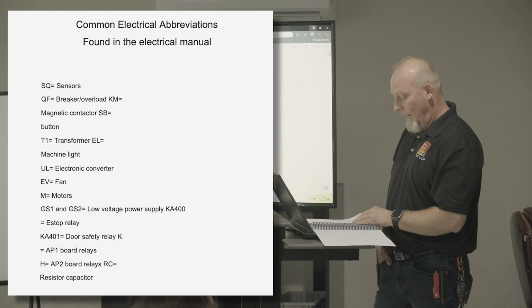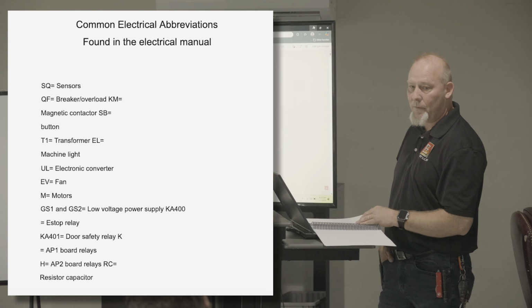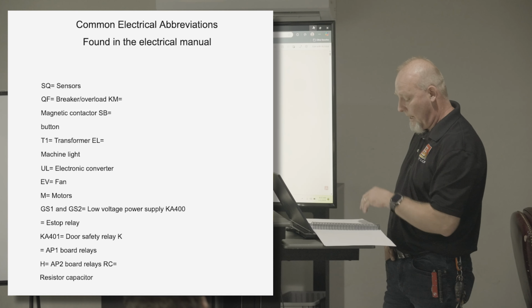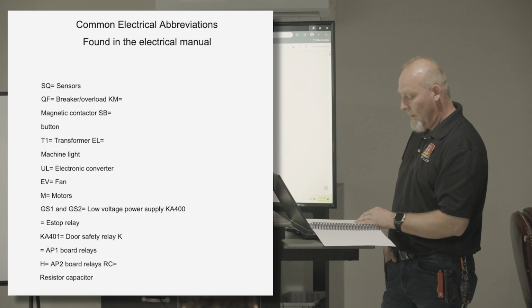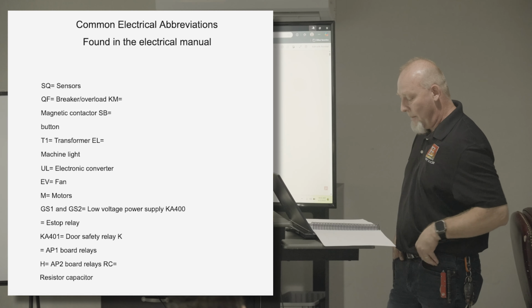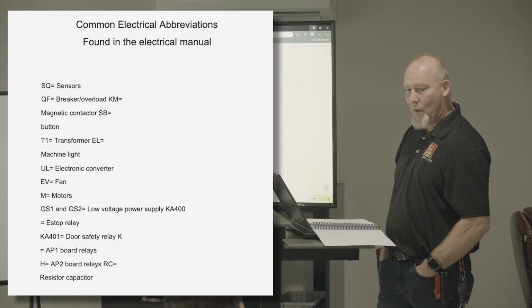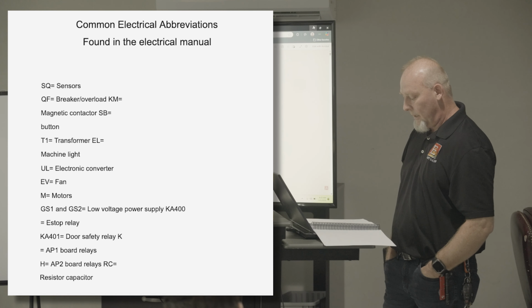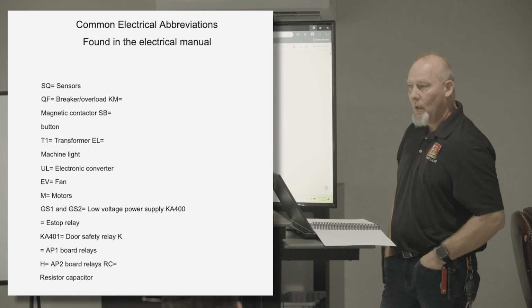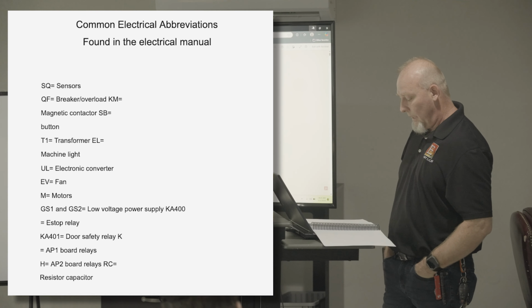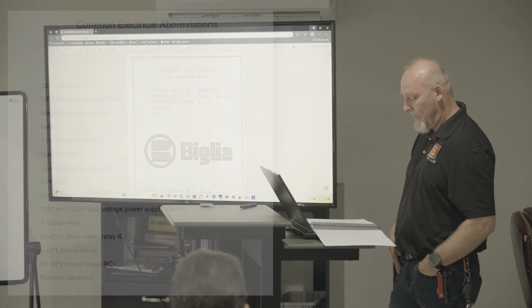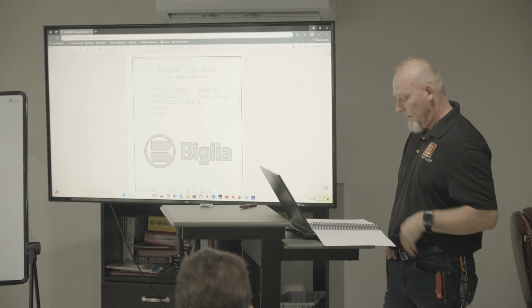The KA400-401 is our e-stop relay and door safety relay. There's been some changes on that now. We still have the KA400 for the e-stop, but now we're going through an AP board for the doors, which we'll see out on the floor. In the manual, K's will represent the relays on the AP1 board, and H's will represent the relays on the AP2. So if we've got something going on in either one, it's pretty quick and easy to reference those.